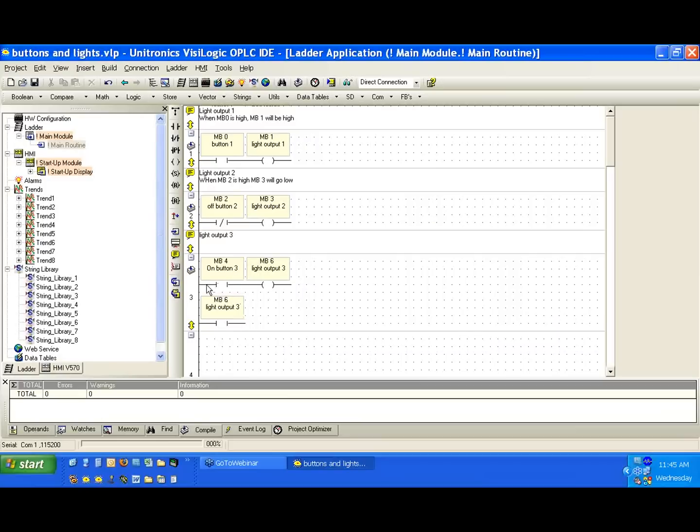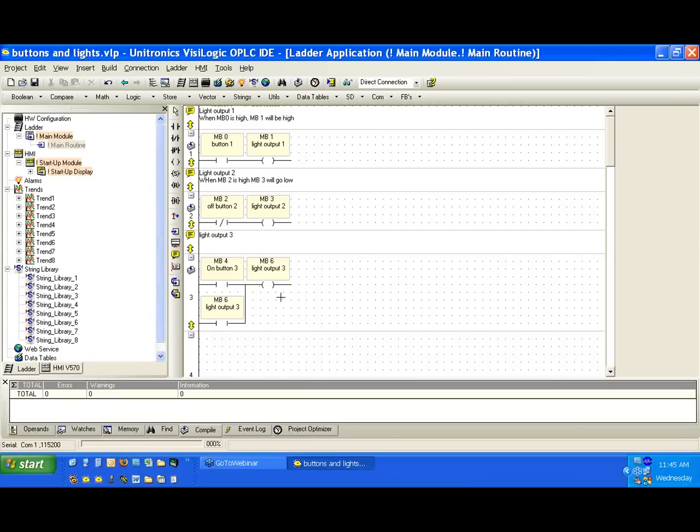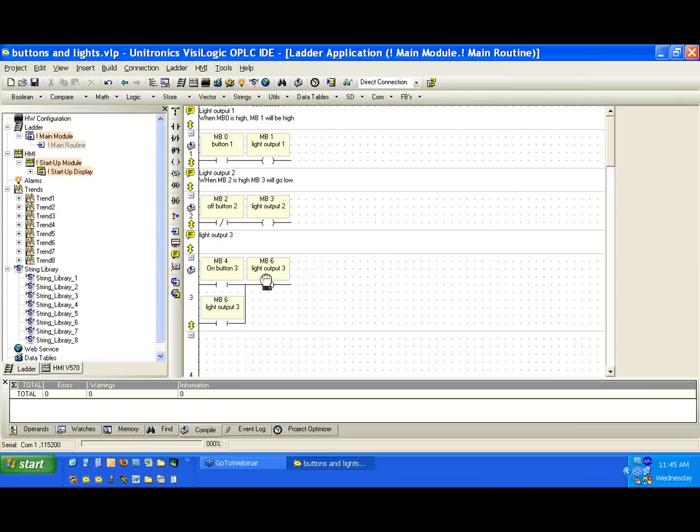Now, what we can do is join these ideas as parallel statements. So we can click on the connect elements. And what we get now is a crosshair on the ladder section. And we can use this crosshair to draw a line. So we're going to connect in parallel the contact of MB4 and the contact of MB6. I'm going to click on the output of MB6 and just draw straight up. Now, notice that when you're using the draw line, you can only connect the end points. I can't just draw into the middle of this and I can't just draw on the side here. The contact always needs to be made at the intersection.